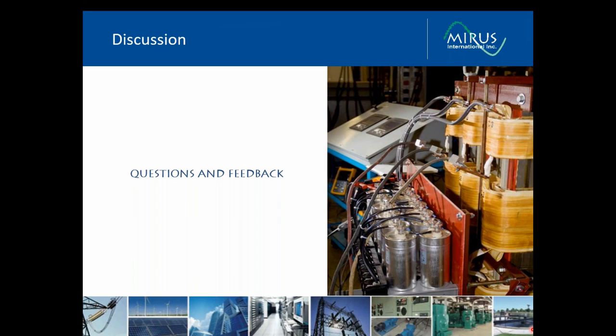I see there's another question up there about active filters having higher losses. What I was referring to wasn't an active filter when I was talking about the losses. I was talking about an active front-end drive. Active filters do have relatively high losses, but the size of the filter would determine the amount of losses that are introduced in the power system. So there might be some applications where a parallel active filter introduces relatively low losses. But I still would expect that the Lineator with a six-pulse drive application ends up with lower overall losses than you'd get with an active filter. So I think that's it for the questions today.